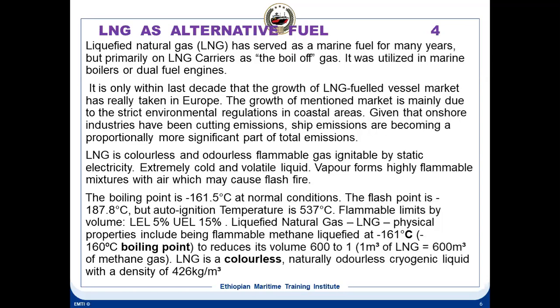So the main things are the boiling point, flash point, auto ignition temperature, and molecular weight also plays a very important role. The molecular weight of LNG is 16.04, whereas the air is 29. So the molecular weight of air is much higher. The LNG molecular weight in the vapor state is 16.02. That is why whenever the LNG spills out and the vapor becomes warmer, around minus 106, it becomes lighter than the air.